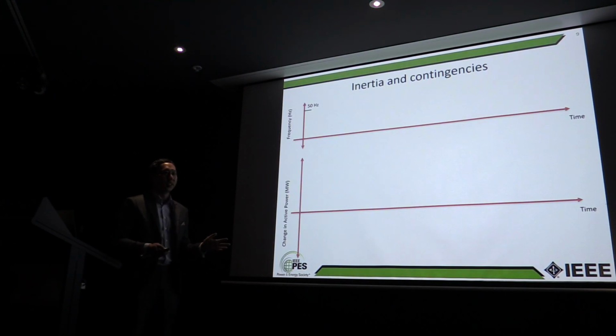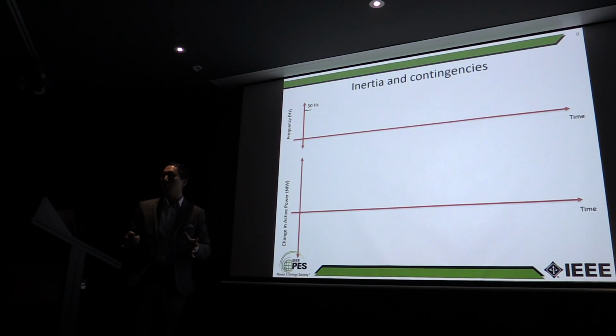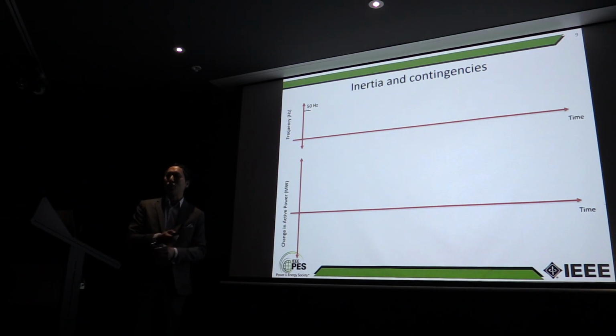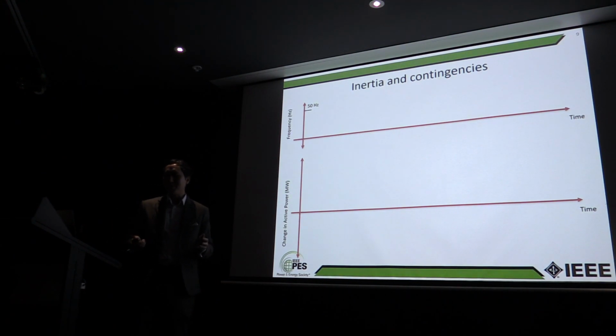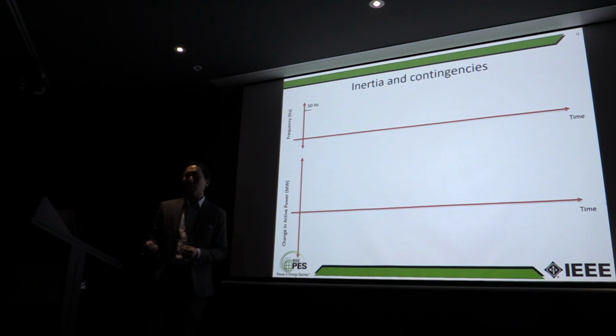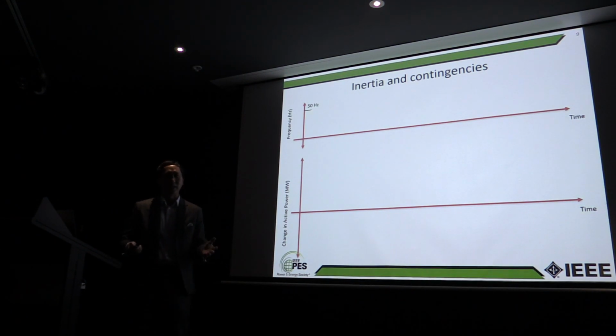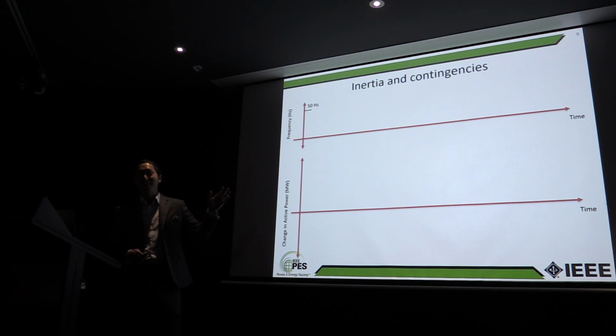So inertia and contingency. This is the second big piece here. A contingency, if you don't know, is basically any undesired system event. It could be a generator just tripping off the system. We didn't want it to happen, but it happened. Or it could be a load coming off, or lightning striking a tower, and then the tower tripping, load coming off. That's a contingency. When I say contingency here, I'm really mainly talking about a generator contingency.